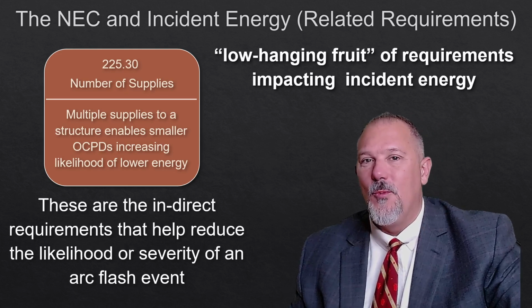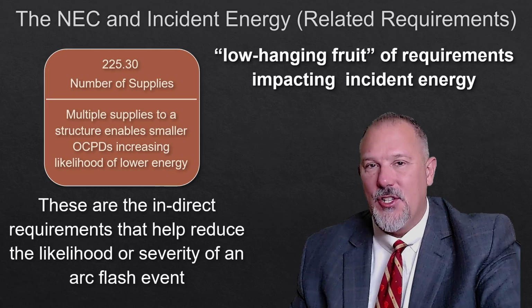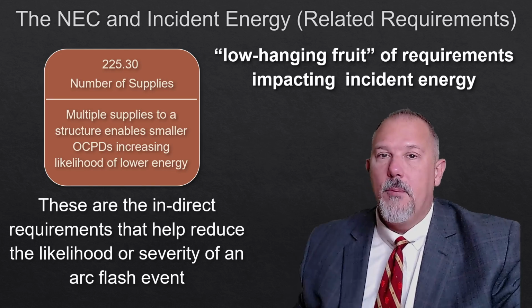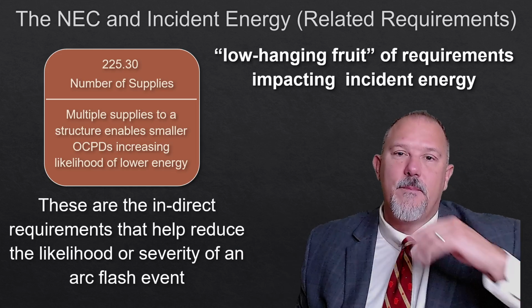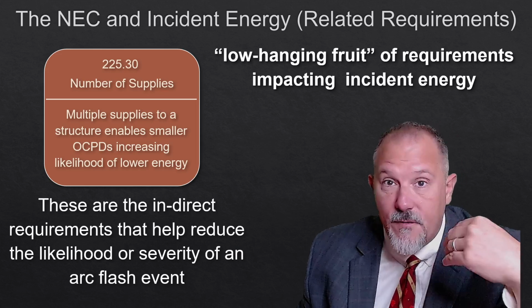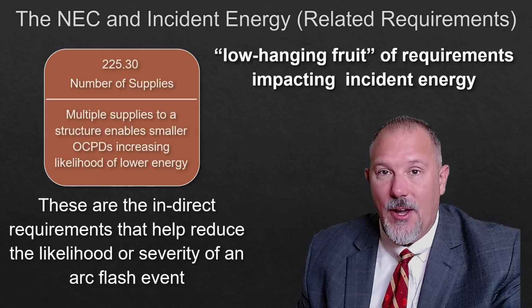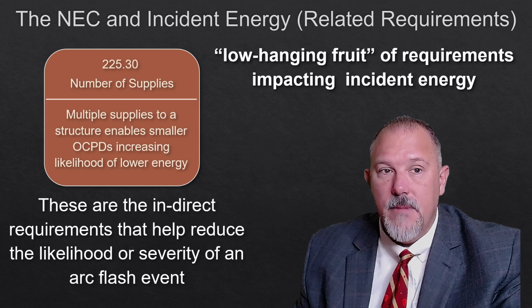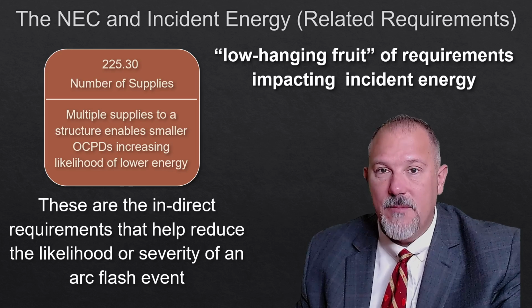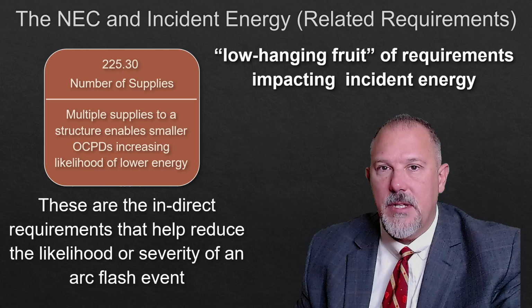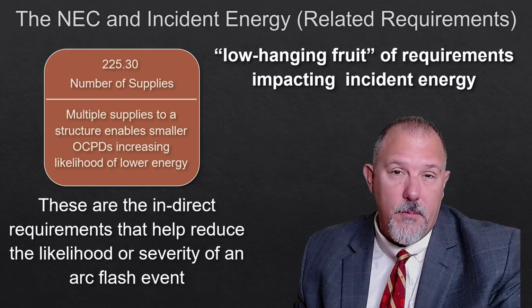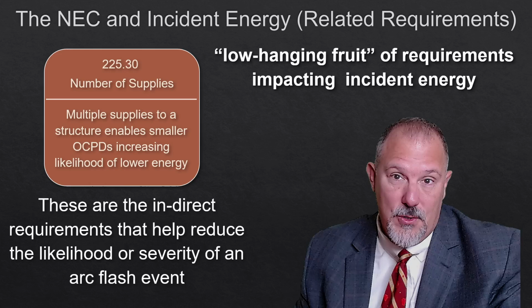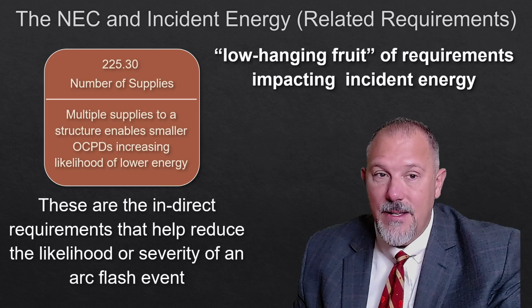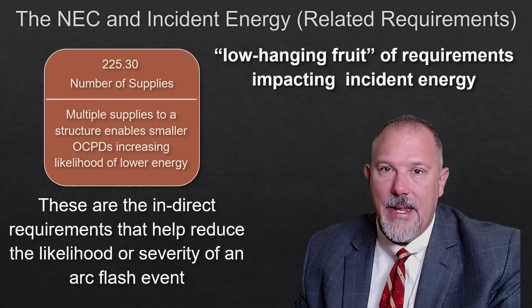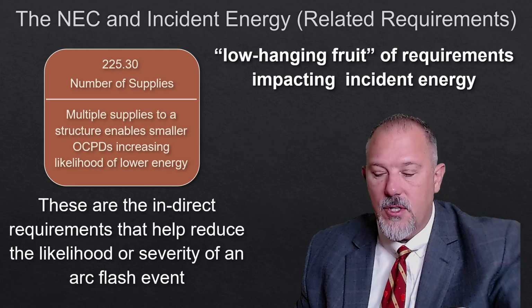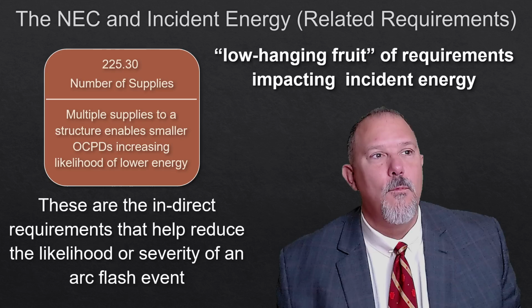And then that issue was exacerbated when we made changes in Article 555 for marinas, where we put ground fault protection of equipment at the service entrance, upwards of 100 milliamps, for feeder protection going onto a dock. And that's because of all the electric shock drowning issues that we're seeing in marinas. Well, that required possibly a change in the design, which would mean you need to pull possibly 2 or more feeders out to a dock. And what is a dock? It's a structure. So it would violate earlier versions of the National Electrical Code, but the 2020 said, no, we're not going to call that.